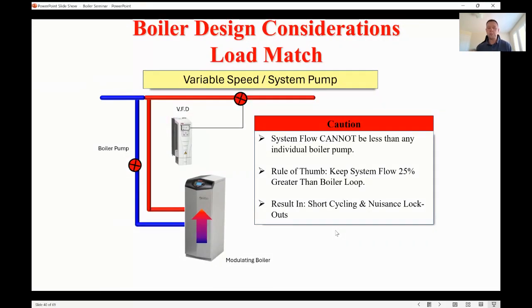So the boiler is going to do a couple of things. One, it's going to alter its PID algorithm, so instead of maybe charging the set point, it approaches it much slower so you don't overshoot. The other thing it's going to do is it's going to know there's less load on the system. It's going to look at its system supply sensor, its inlet and its outlet temperature, and determine if it's going to be in recirculation mode, and it'll start ramping that pump down to try and avoid that situation as well. So you always have less flow in that boiler loop than you do in the system loop.